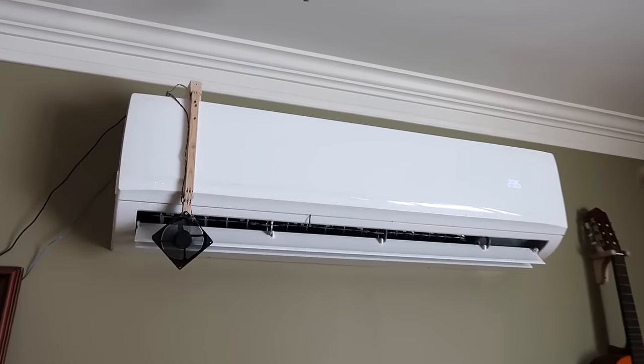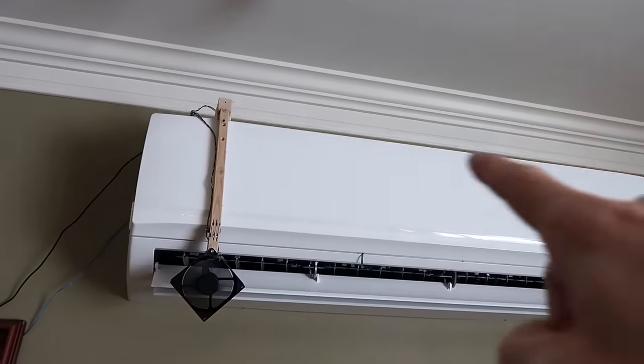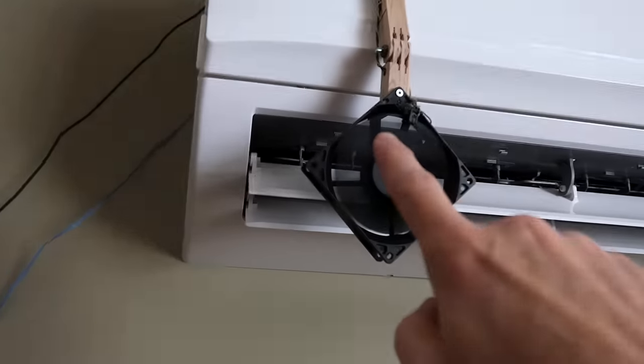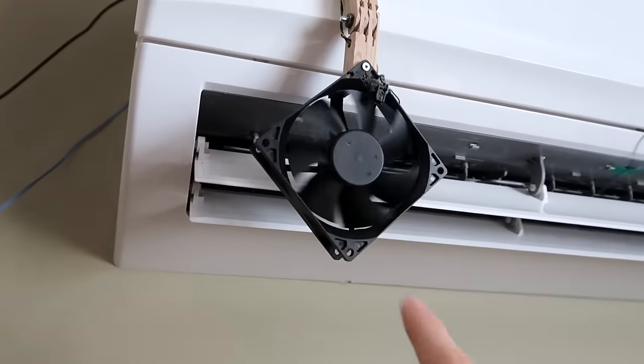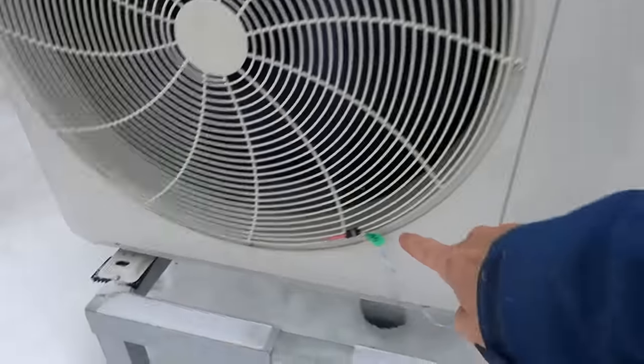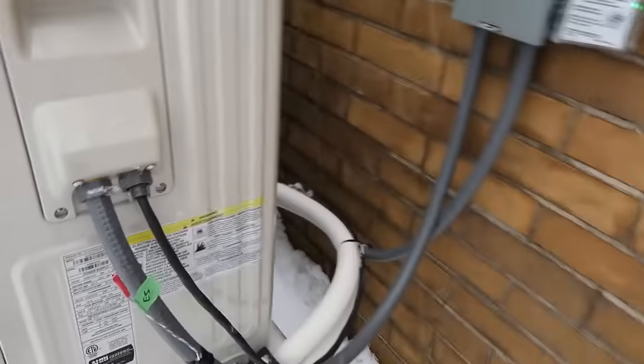And just to observe how this thing is doing, I've got a couple of temperature sensors where it sucks in the air, another one where it blows out the air, plus a homemade anemometer to gauge how much is blowing. I also added sensors to the outside unit. There's one here, another one inside, one for ambient and then one on the back where it sucks it in. And I put those sensors on back in December before we had snow, it was way easier then.